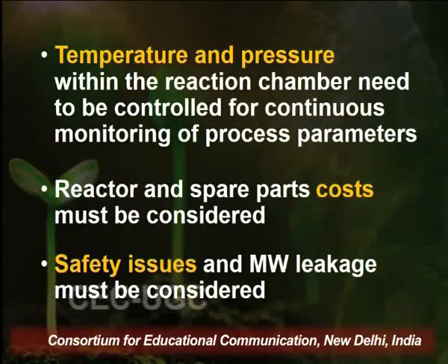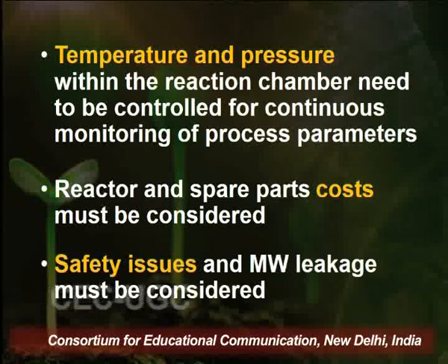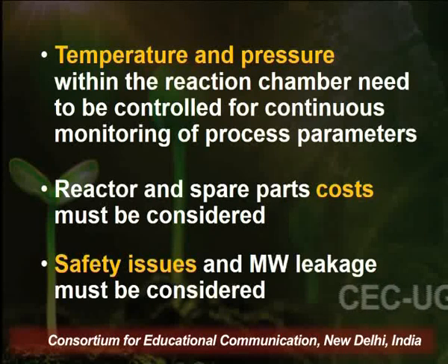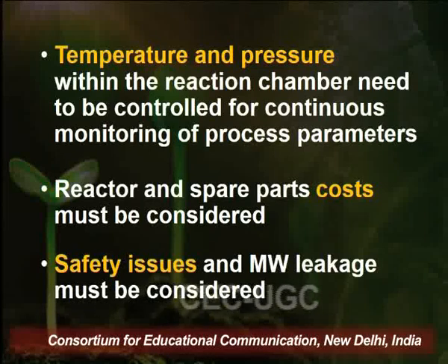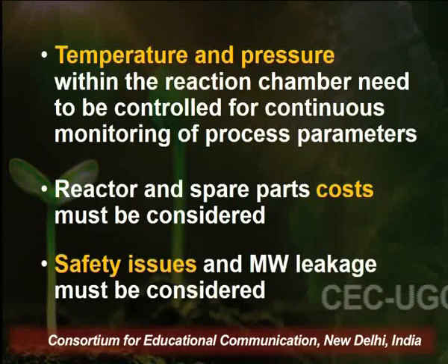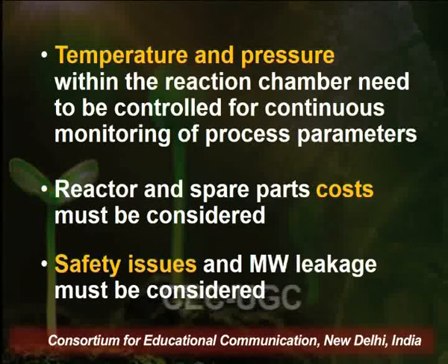Next thing which has to be kept in mind is the temperature and pressure. There are microwave reactors which operate at atmospheric pressure, and there are microwave extractors or reactors which operate under pressure above the atmospheric pressure. So in such cases, one has to be very careful while designing the microwave reactor in order to control the temperature and pressure. Even if you are working at higher pressure, you have to design a reactor in such a manner that increased pressure or temperature should not have any kind of safety issues.